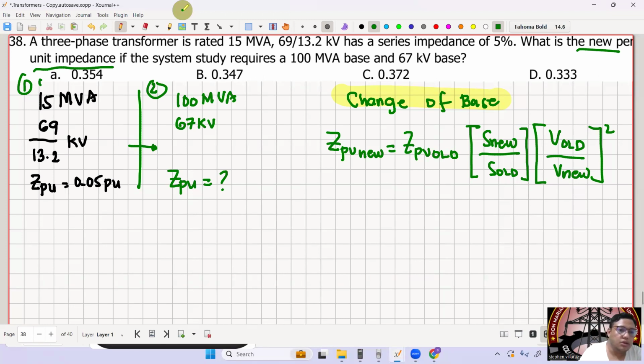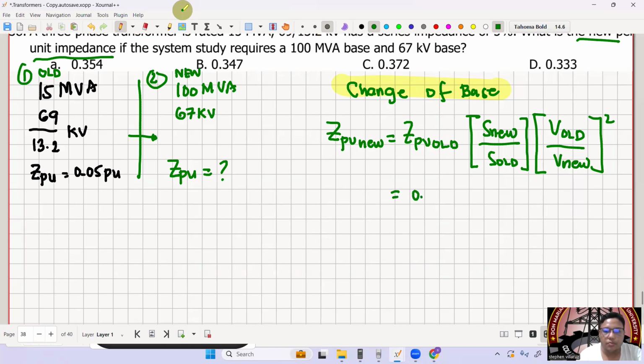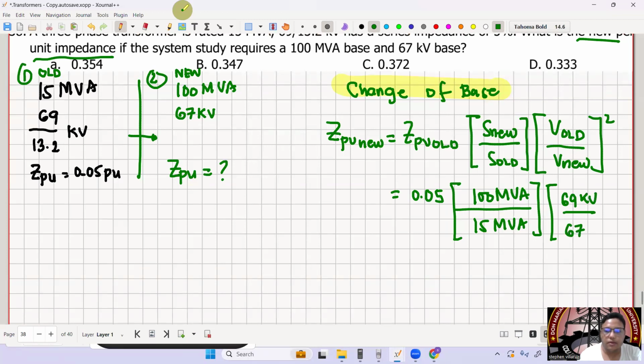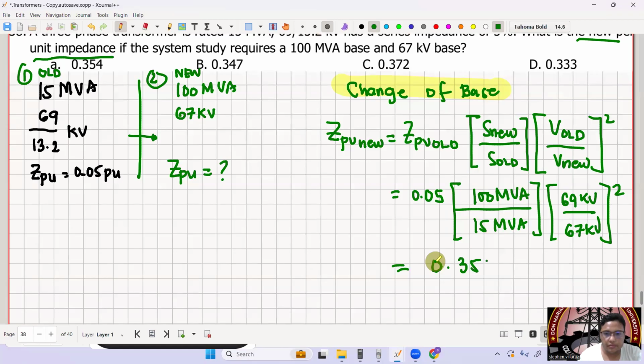Okay? So, nasan yung old? Ito yung condition 1. So, saan yung new? Yun yung condition number 2. Okay? So, therefore, this is now equal to what? 0.05 multiplied by S new natin, so 100 MVA over 15 MVA, multiplied by V old, that is 69 kV over 67 kV. So this is the quantity squared. So ilan to? So 0.05 multiplied by 100 over 15 multiplied by the quantity 69 over 67 squared. So therefore, this is now equal to 0.3535 per unit. And this is letter A.